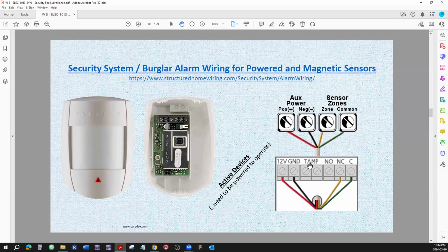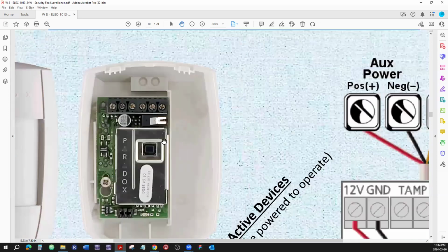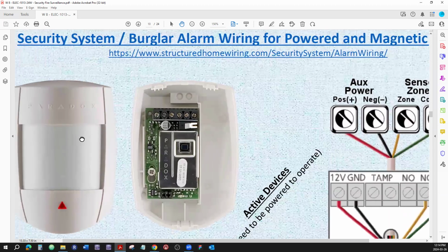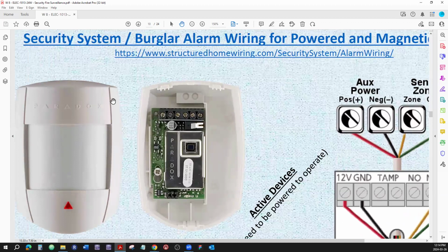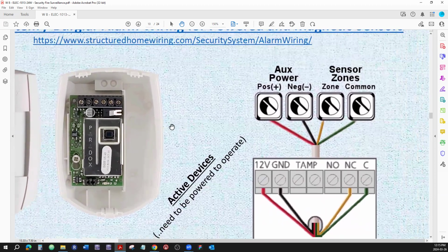Also, you see something like the temp—it's for a tamper switch. Now, the tamper switch, you'd see it right here. If somebody is tampering with that—once you put the cover on, you snap it, and there's a pusher on the other side that pushes that in, so the tamper switch is closed. As soon as you take the cover off, that switch is released and opens, and the system can go into alarm. So you would wire that thing in series with this zone sensor.